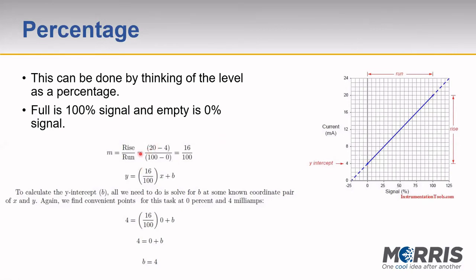So basically, they do this. They're trying to find M in the y equals mx plus b formula. You got the rise over the run. There's your 20 milliamps minus your 4 milliamps. There's 16 milliamps. 100% signal, 0% signal equals 100% right here.